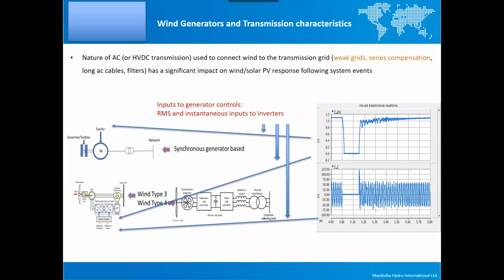One other point to highlight as a technical challenge: both synchronous machines and inverters have control systems. Control systems make their decisions based on measurements coming from the grid, because you are trying to control the power and reactive power, or power and voltage, of the grid. So you need to know the power level and voltage of the grid at that point as an input to your controller. Both of these controls, exciters and governors of synchronous machines, and inverters, need measurements from the grid.